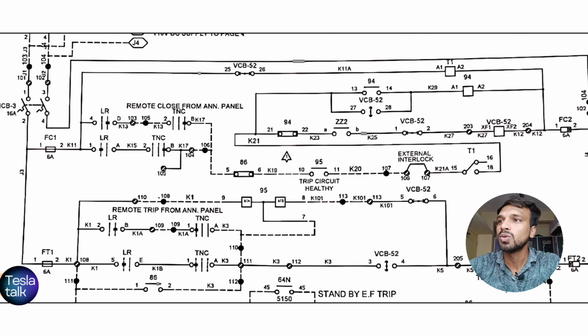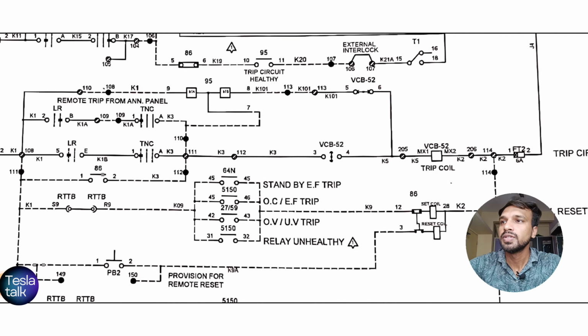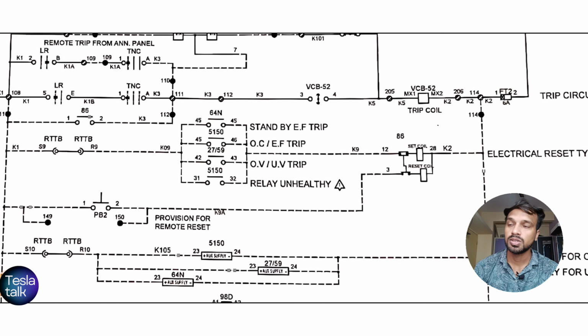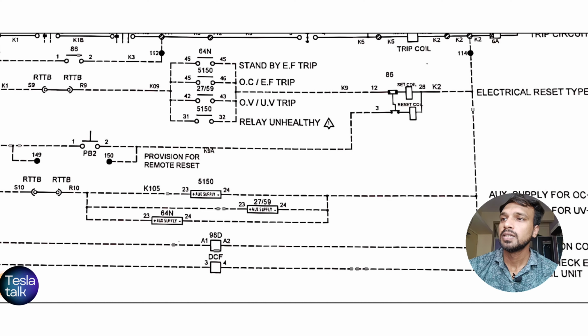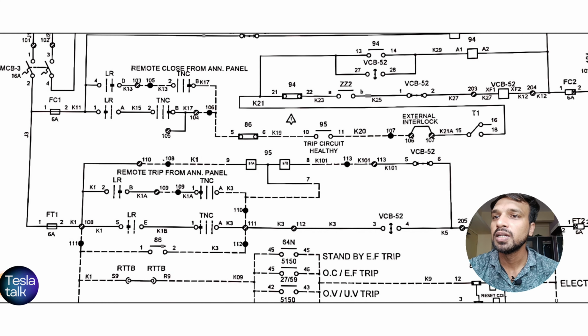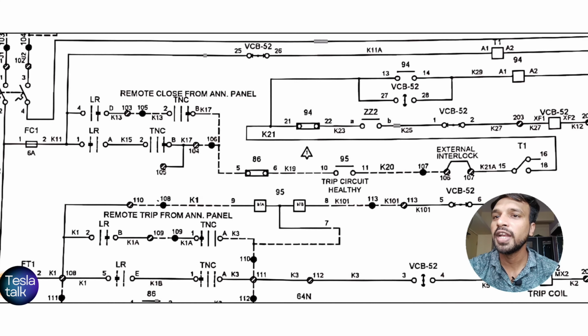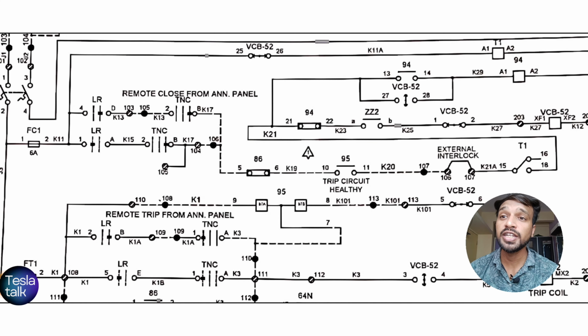We will see then the closing circuit, which is used to operate the breaker to close, which will allow the current to flow through the system. So the closing operation starts with the remote close command coming from the annunciator panel. You can see here the remote close from annunciator panel. This command is generated from the annunciator panel. You can also locally close the breaker; you can see here the local remote switch is given. In the previous video we have seen how a local remote switch works. The remote close command is coming from the annunciator panel.